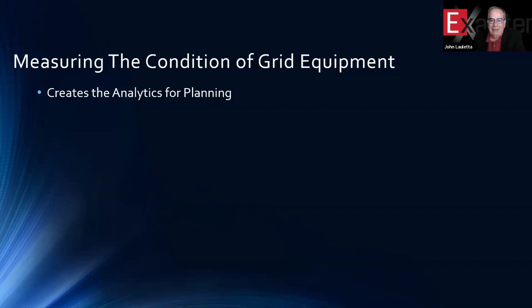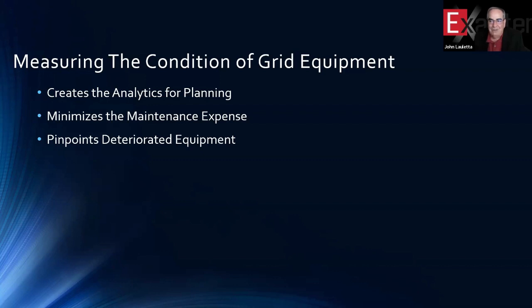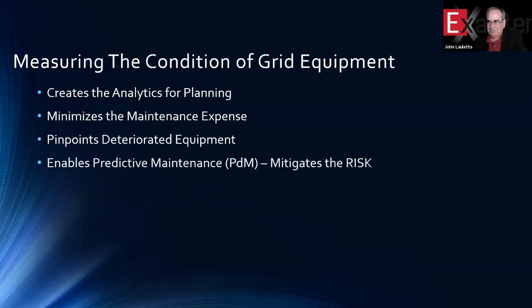So how do you do this now? How do you actually take care of the problem? Well, you create analytics for planning. You find out where the problems are occurring, and you take direct action to locate the problems on your grid. This minimizes the maintenance expense because if you wait for the outage, it's the most expensive replacement program you can have. You need to pinpoint the deteriorated equipment, not just to this pole, but to that insulator on the field side of the bottom crossarm. That's the one problem area that you've got to take care of.